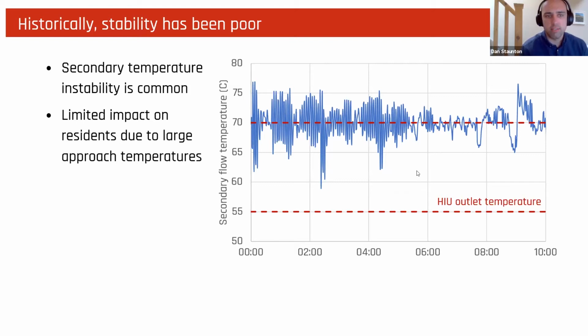Historically, this has had a relatively limited impact on residents. We've designed with relatively large approach temperatures between secondary flow temperatures and HIU outlet temperatures. So on the scheme that this was taken from, whilst the plate was delivering at 70 degrees, the HIU was only delivering 55 degrees to residents. The plate could therefore vary around 10-15 degrees from set point without any impact on residents. Next slide.